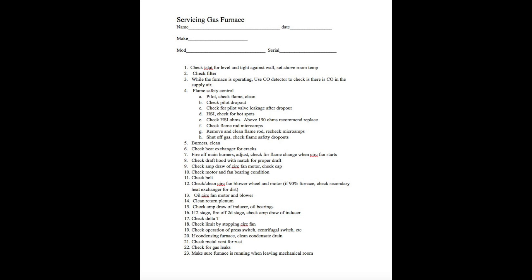We need amp draw of the circulating fan motor. You're using your clamp meter to do this. You are comparing it to any information you have. You may have to pull a fan motor to actually find the amps for that motor. But it should be running at or below rated load amps. While you're at it, pull the cap off and use your cap tester to check the cap and see if its strength is proper.